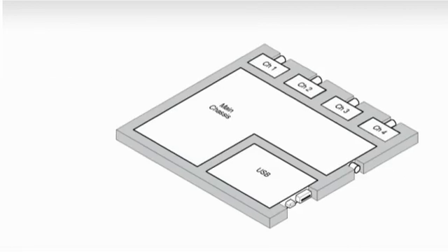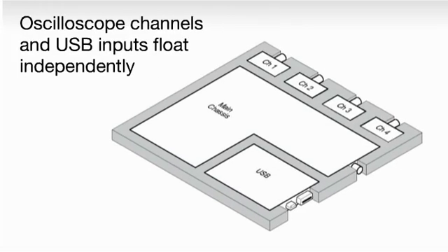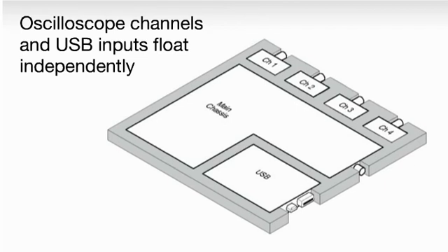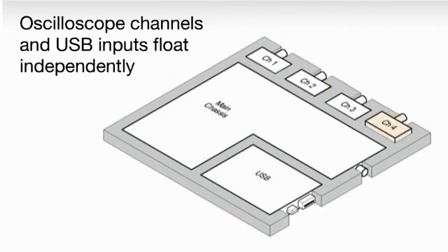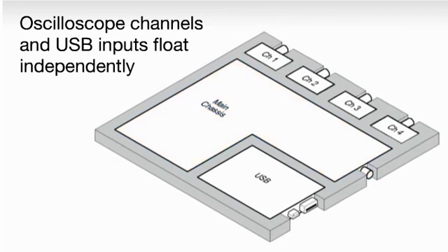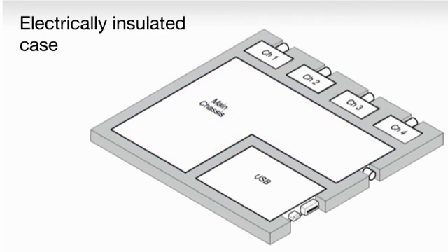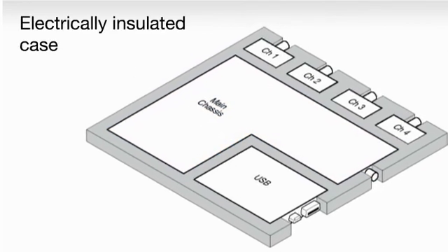This handheld oscilloscope utilizes a unique architecture that fully isolates all of the input channels and communication ports from the main chassis and from each other, enabling you to safely make high voltage measurements when your signals are floating or not referenced to earth ground.